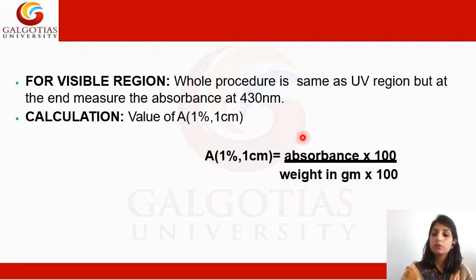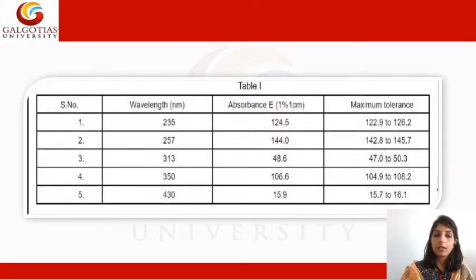So whatever absorbance you get, you put that absorbance over here and multiply by 100. Then the weight of potassium dichromate that you have taken, you put that weight over here and multiply it by 100. So you will get a value of A 1%, 1 centimeter. 1% is the concentration, and 1 centimeter is the path length of the cuvette that you are using. Like this, you will calculate A 1%, 1 centimeter values for different wavelengths, and you will check whether you are getting the absorbance value within the tolerance range.